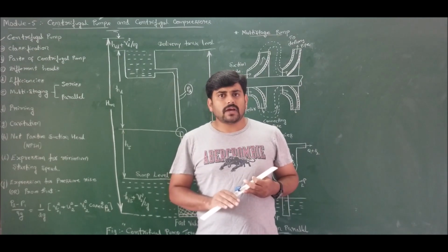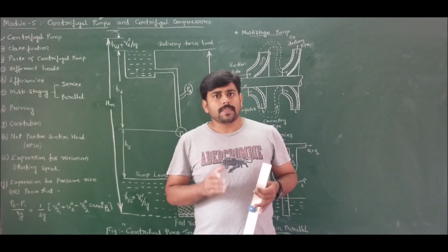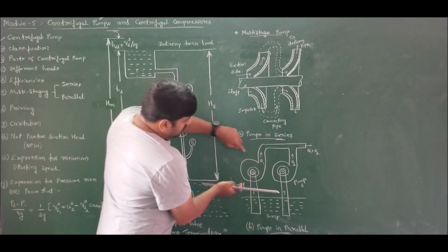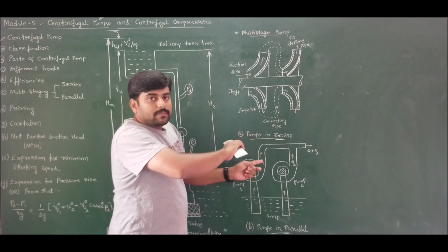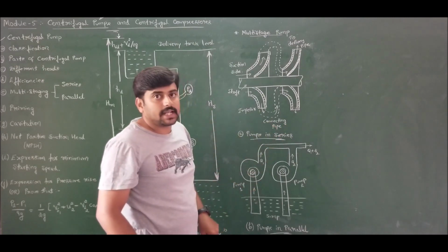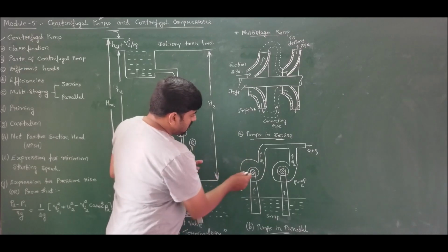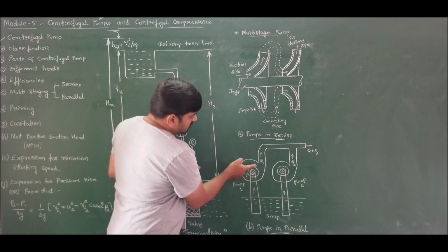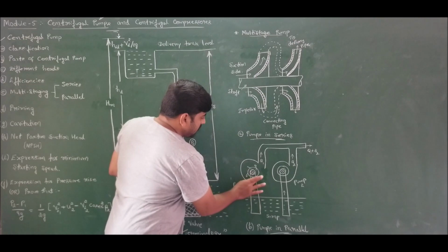The casing might have different types. There are many types of casings. Always the casing will have divergent sections towards the delivery pipe. If I take the casing, the outer part will be a diverging section connecting the delivery pipe. This is because it ensures that pressure rise takes place in the direction of flow. So when you draw the casing, if water flows outward, the cross section area here should be less and here should be more, which I have drawn contradictory to it.